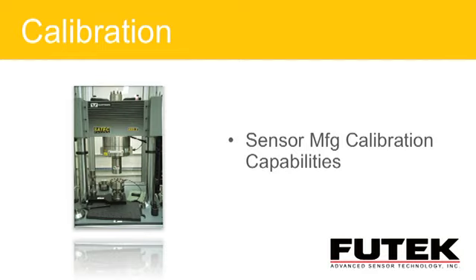On top of this, some calibration may require being done under pressure or vacuum, or there may be a certain range you need calibrated. For example, you have a 10-pound capacity sensor but primarily use it in the 2-pound range, so you may want additional calibration points in that lower range to characterize the product. You don't really care about the higher range; it's there more for overload capability so you don't damage the sensor.